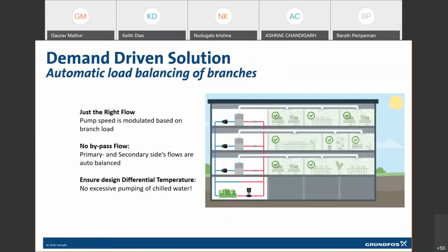The third point is a demand-driven solution, and it is very important when we look at a system where you ensure that the system is meeting the requirement of the chilled water as the load changes. If you look at this pump, which is connected with this particular AHU, it is being controlled based on the temperature sensor from this AHU. This pump is controlled based on the temperature sensor from this AHU, and so on and so forth. So there is a localized control. The entire intelligence is in the pump at that particular location, and that is what we mean by demand-driven solution.